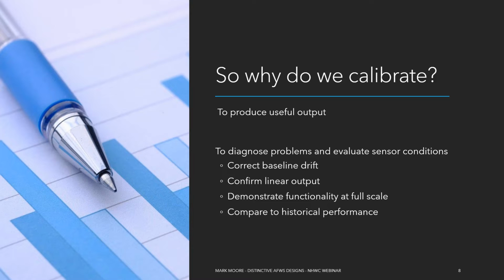It demonstrates functionality at full scale, and I want to take a moment and focus on that real quick, because that's a really nice advantage when we're talking about calibration, especially when it comes to PTs and bubblers when they allow for it, is that we know after we calibrate that our sensor is going to work the entire range that we calibrated across. You're sitting there on a day that it's not flooding and you are testing your stuff and you're hoping that it works when the water's high. But a calibration is really when you're testing that. And when you calibrate it up to 20 feet and you get good trustable data, you can be confident that when the water level is actually 20 feet deep, it's going to be accurate. So it's a really nice feature to be able to demonstrate that it works at full scale.